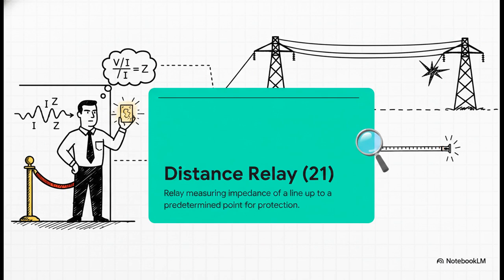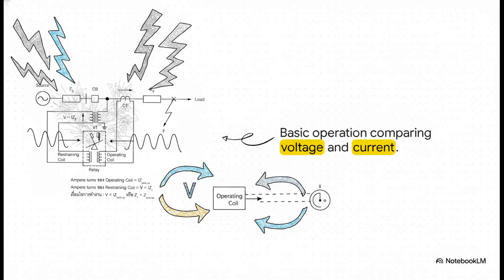Because the impedance of a transmission line is inherently proportional to its actual physical length, this clever little device can literally measure the electrical distance to a problem. Now, to actually see this electrical world, our bouncer needs a bit of help. I mean, the relay can't directly handle the hundreds of thousands of volts coursing through the main line. It would fry. Instead, it uses a VT, or a voltage transformer, and a CT, a current transformer. These step those massive, lethal numbers down into a safe, manageable scale. By constantly comparing the voltage against the current, essentially checking the restraining coil against the operating coil, it can monitor the real-time operating conditions without blowing up.